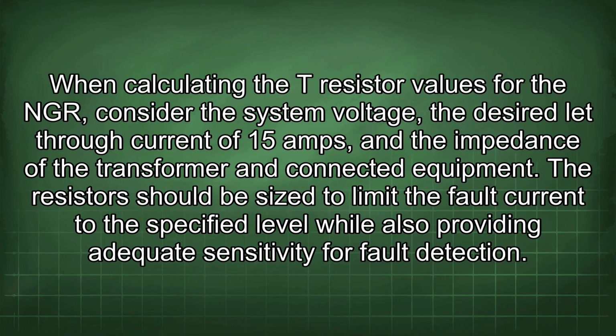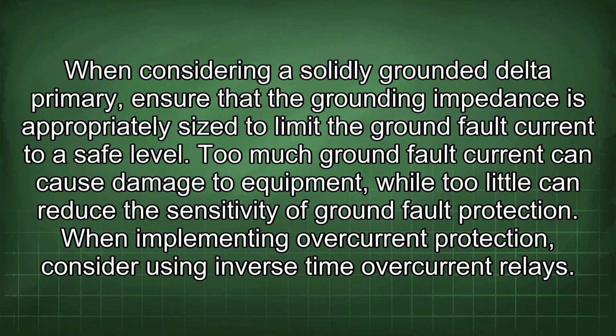When calculating the T resistor values for the NGR, consider the system voltage, the desired let-through current of 15 amps, and the impedance of the transformer and connected equipment. The resistors should be sized to limit the fault current to the specified level while also providing adequate sensitivity for fault detection. When considering a solidly grounded delta primary, ensure that the grounding impedance is appropriately sized to limit the ground fault current to a safe level.